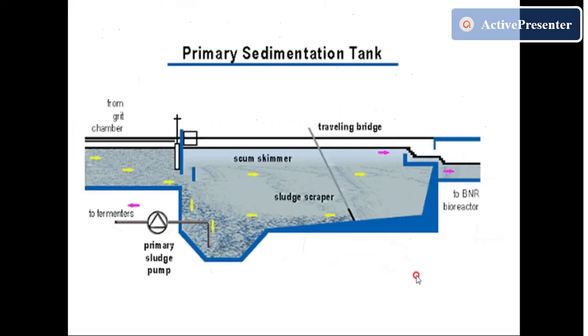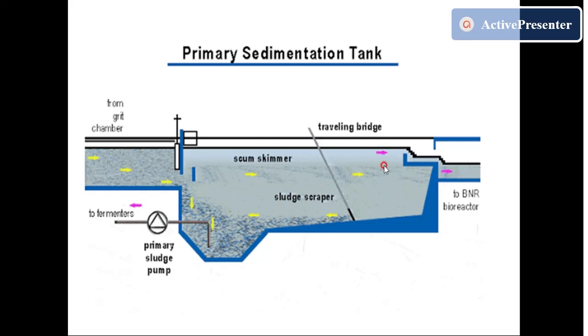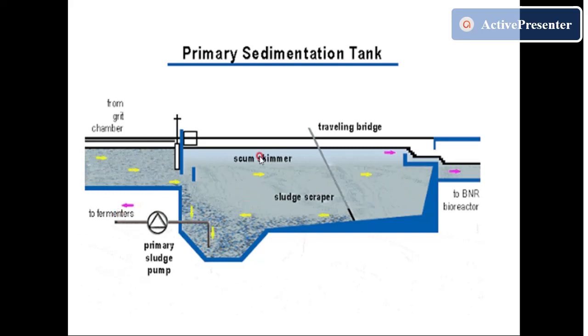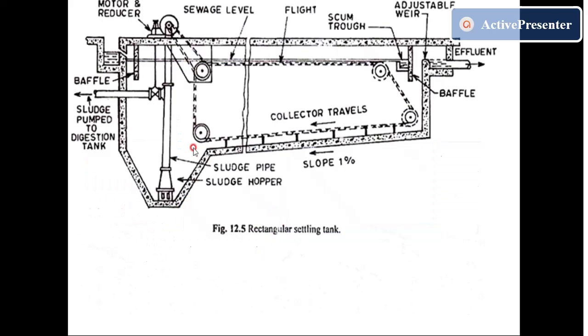Here you can see water coming from the grit chamber — which is essentially screening — moving slowly from inlet to outlet. As water moves, particles settle and are deposited into a small collection tank at the bottom. Floating matter, called scum, is removed by a scum skimmer. In the top view, this is a rectangular sedimentation tank. A chain arrangement collects deposited material and brings it to the sludge tank.